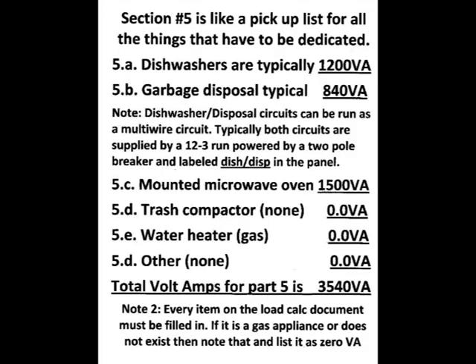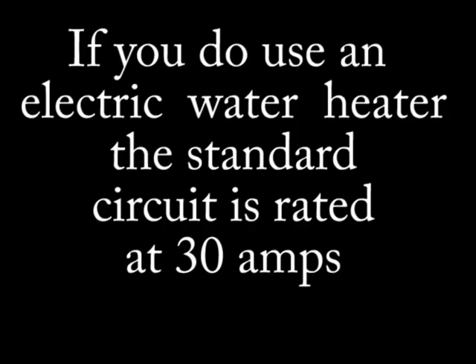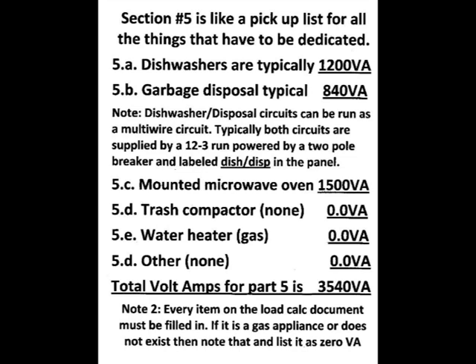Section 5 is like a pickup list for the things that have to be dedicated but aren't always listed on the load calcs, though they're required in the code book. Dishwashers are typically 1,200 volt amps. Garbage disposals are about 840 volt amps. Mounted microwave ovens are always 1,500 volt amps. Don't leave anything blank on your load calculation application — if you don't have it, just write 'none' and put in zero volt amps. No trash compactor: zero volt amps. Water heater is gas: zero volt amps. If you do use a water heater, rate it at 30 amps. Total volt amps for section 5 is 3,540.